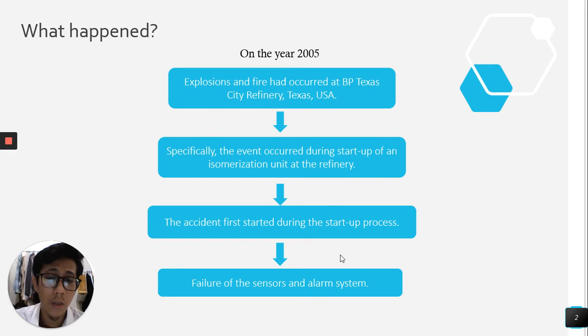When there is a failure of this liquid height sensor, it cannot detect when there is excessive flow of liquid into the tower. Plus, when there is a failure of the alarm system, when the liquid flows excessively over the limit, it cannot detect it, and it cannot alert the operators. So that is what started the accident.